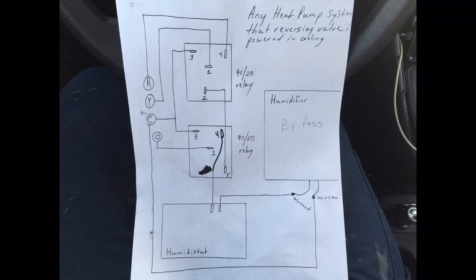On the 9293 below it, you've got common at terminal 3 and power from the O terminal, or the reversing valve, at terminal 1. The 9293 has an additional leg that is normally closed, and the one that's blacked out below the number 1 terminal is your normally open, very similar to the 9290, but not exactly the same, because it actually has an additional terminal at terminal 5. So that relay, the 9293, when power goes to orange, you energize the 24 volt coil and you open the contacts between number 4 and number 5.